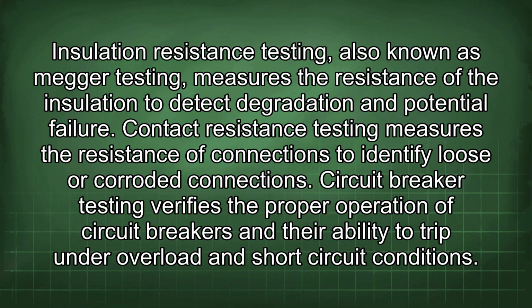efficiently. Insulation resistance testing, also known as megger testing, measures the resistance of the insulation to detect degradation and potential failure. Contact resistance testing measures the resistance of connections to identify loose or corroded connections. Circuit breaker testing verifies the proper operation of circuit breakers and their ability to trip under overload and short-circuit conditions.